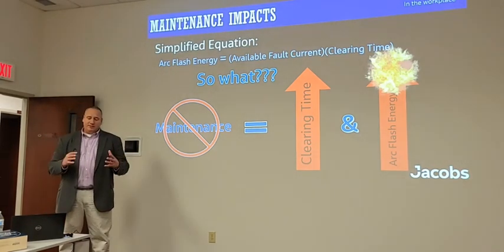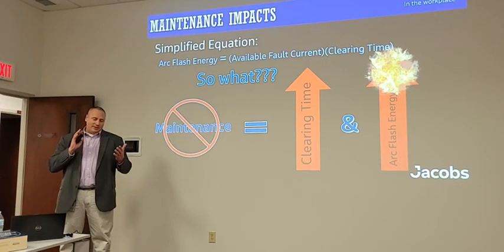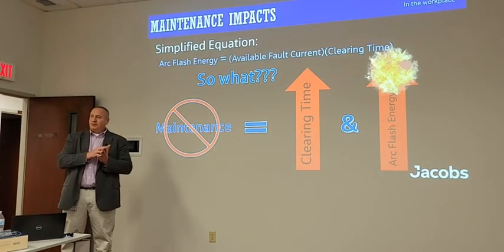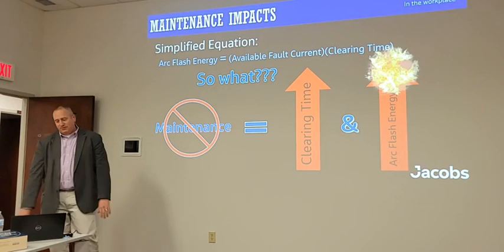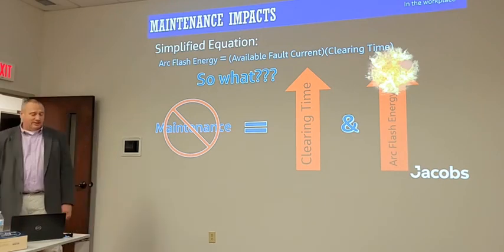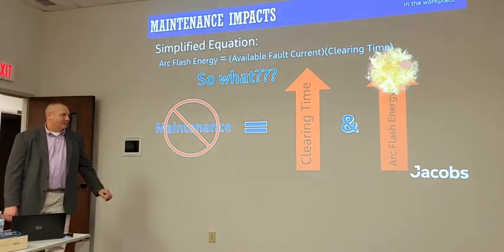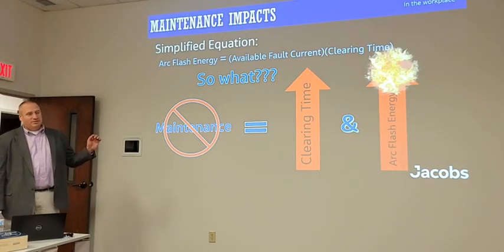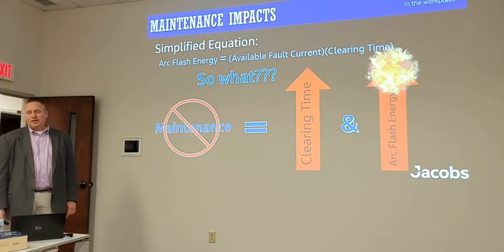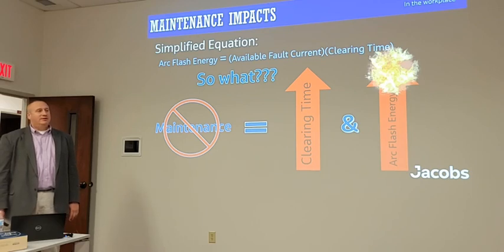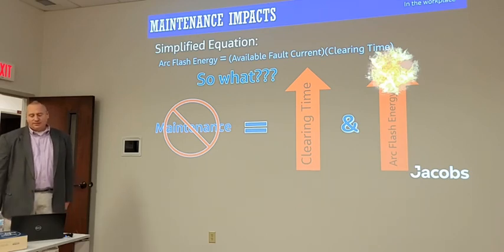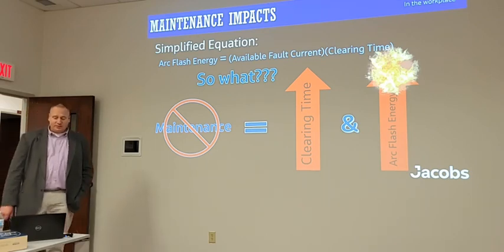You know, if they get gummed up, or if you have breakers that the contacts weld closed and they're not going to break or trip. There's all kinds of things that can impact your clearing time due to improper maintenance. And so maintaining our equipment is very important to the safety and the arc flash protection of employees.